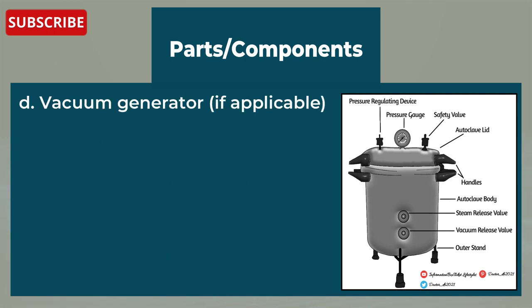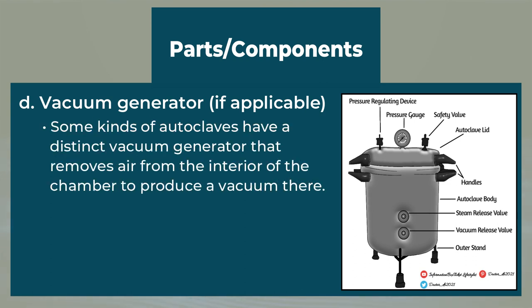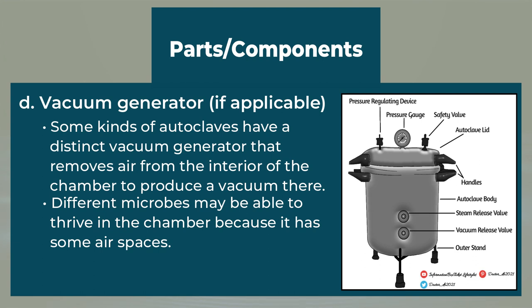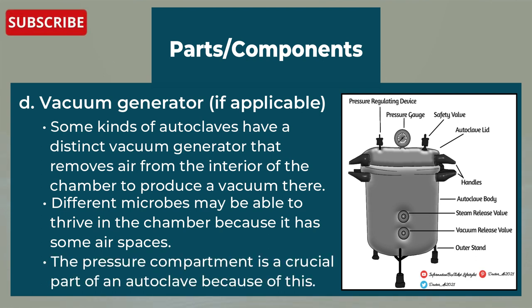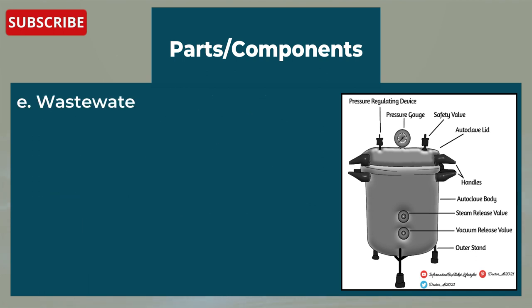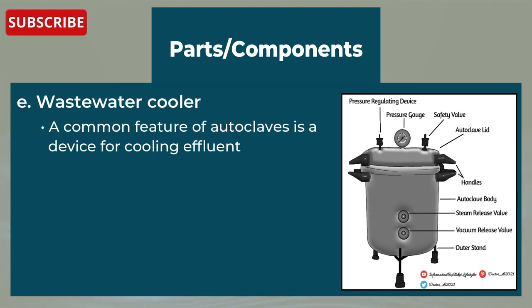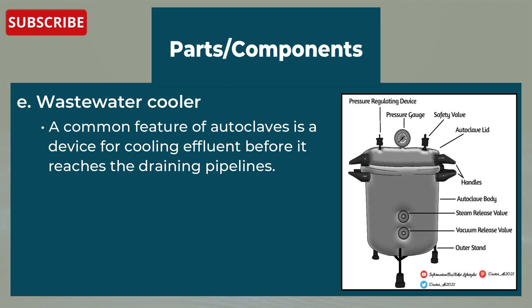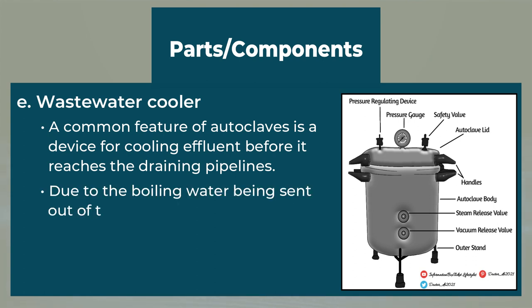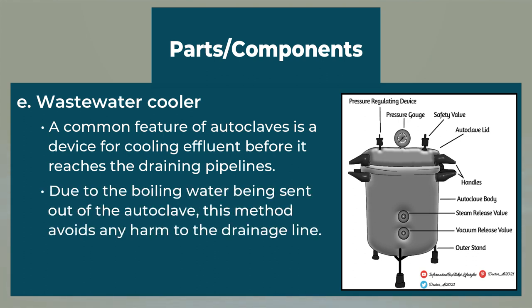Some types of autoclaves have a distinct vacuum generator that removes air from the interior of the chamber to produce a vacuum. Different microbes may be able to survive in the chamber because of air spaces, which is why the pressure compartment is crucial. Lastly, a wastewater cooler is a common feature of autoclaves — a device for cooling effluent before it reaches the draining pipelines, avoiding any harm to the drainage line from boiling water being sent out of the autoclave.